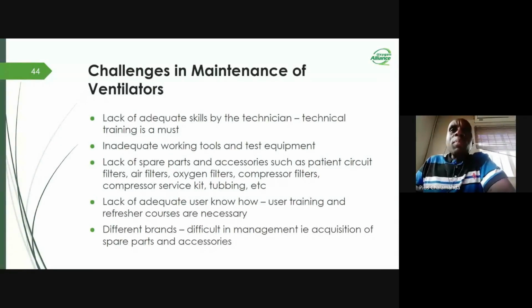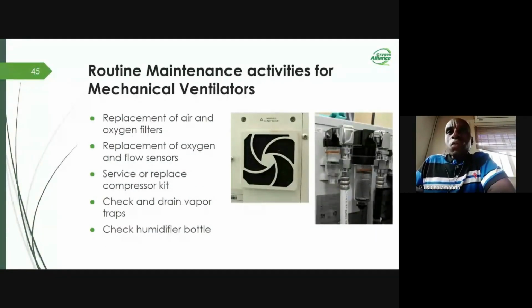Okay, let's wind up. Routine maintenance activities for mechanical ventilators. Time is not on our side, so we have to replace air and oxygen filters, replace oxygen and flow sensors, as I already explained, and service or replace the compressor kit. This is on planned preventive maintenance, which is supposed to be done quarterly, sometimes 6 months, sometimes annually, depending on the manufacturer's recommendations. Yeah, so you have to check or replace the compressor kit.